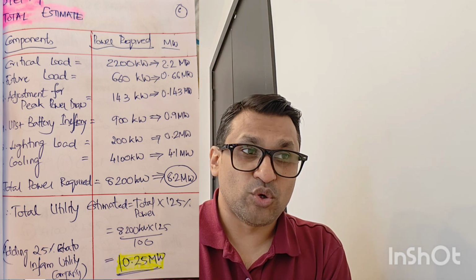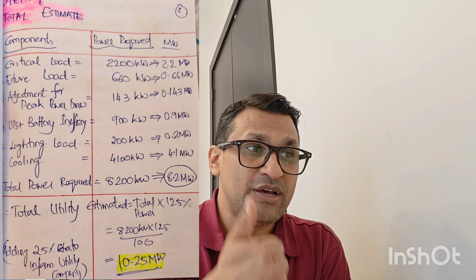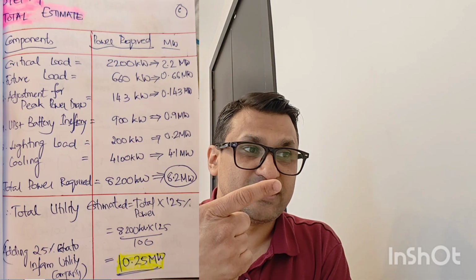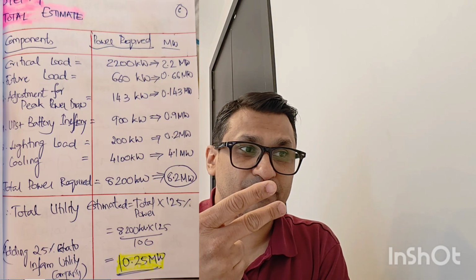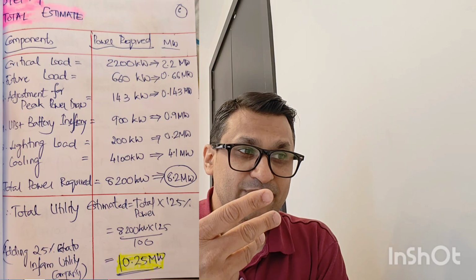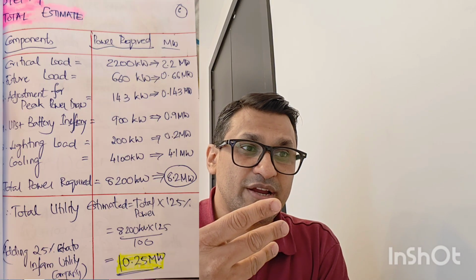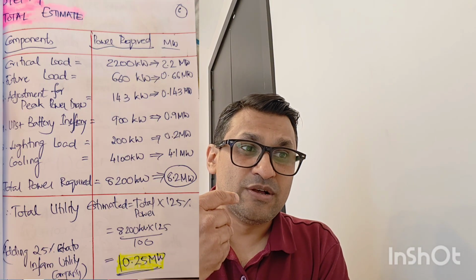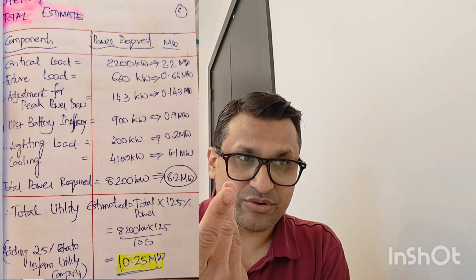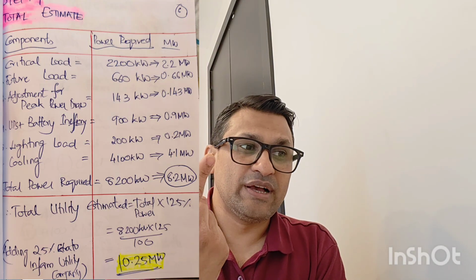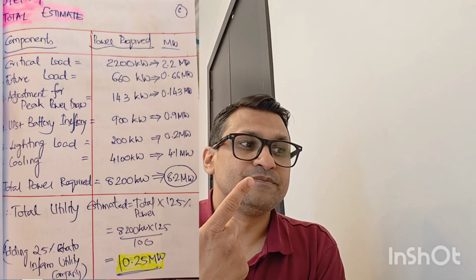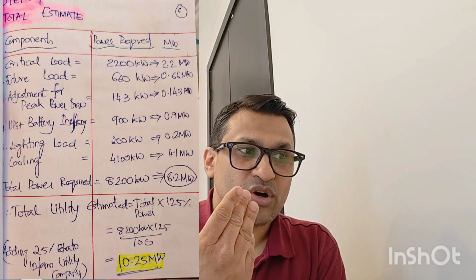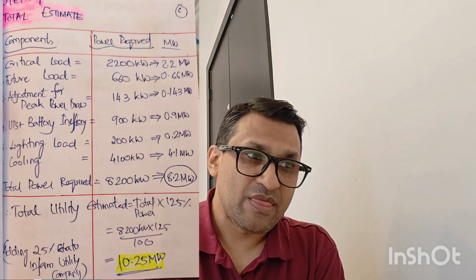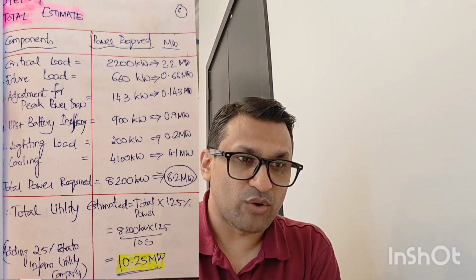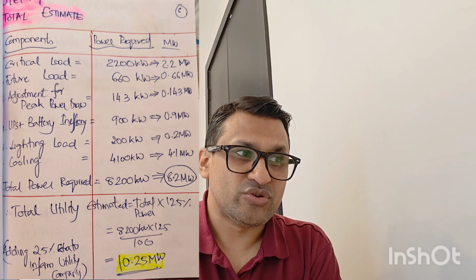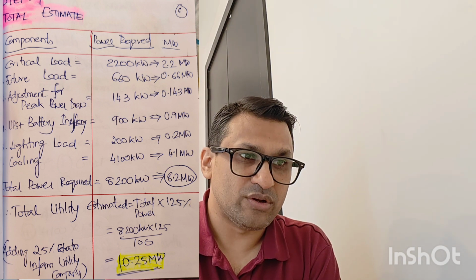The final total estimate, considering the critical load 2200, future load 660 kilowatt, adjustment for peak power 143, UPS battery inefficiency 900 kilowatt, lighting load 200 kilowatt, considering 2 watts per square feet, and cooling 4100 kilowatt, gives a total power required of 8200 kilowatt. If you add all of them, that becomes about 8.2 megawatt.